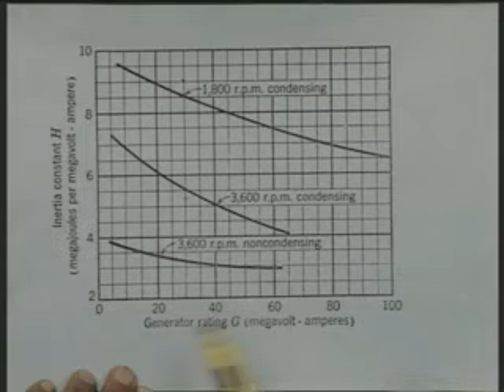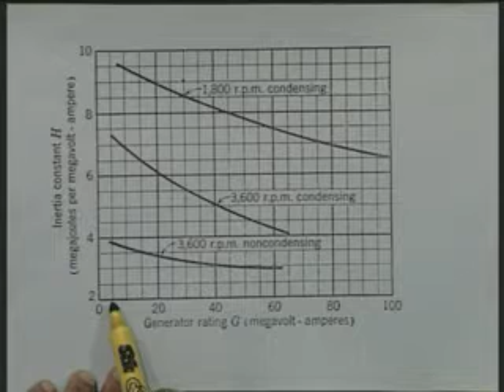This diagram shows the typical values of the inertia constant H for turbo generators. On this axis we have marked the rating of the machine in MVA, and on this axis we have marked the inertia constant H in megajoules per MVA. Now the turbo generators are of different types and different speeds. If you take a turbo generator whose rated speed is 1800 RPM, a 4-pole machine, then the variation of the inertia constant is shown by this graph. When the rating varies from about 10 MVA to say 100 MVA, the variation of H is in the range starting from about 9.5, it goes to 6.5.